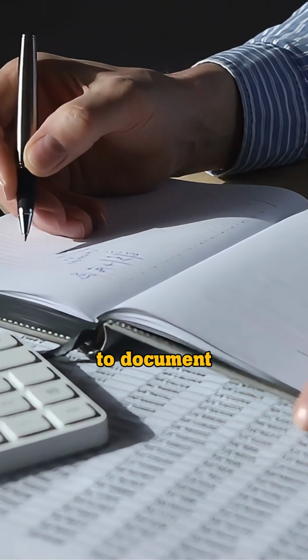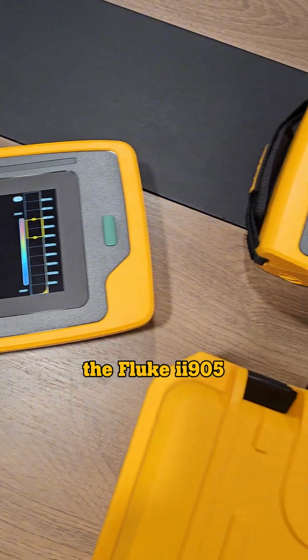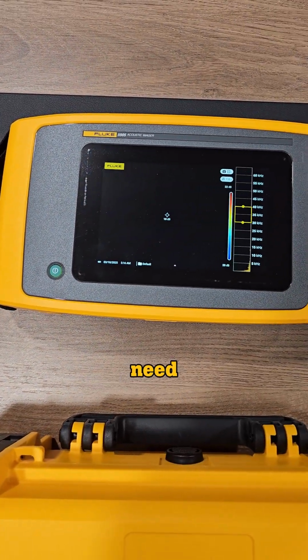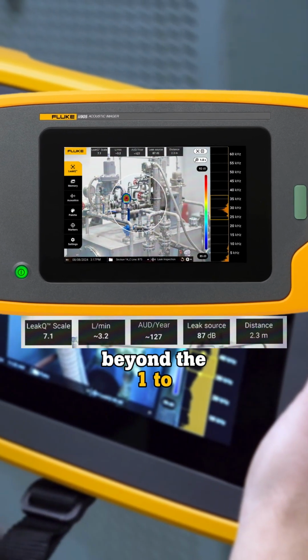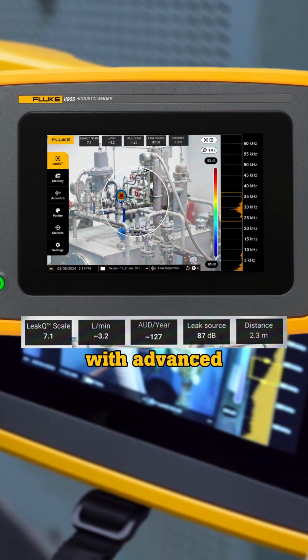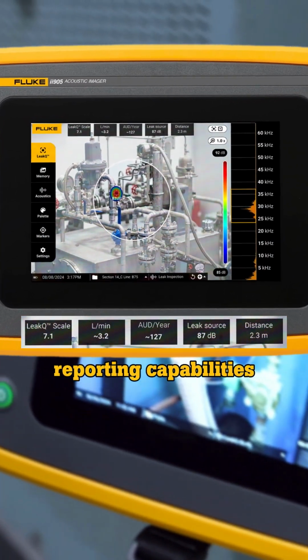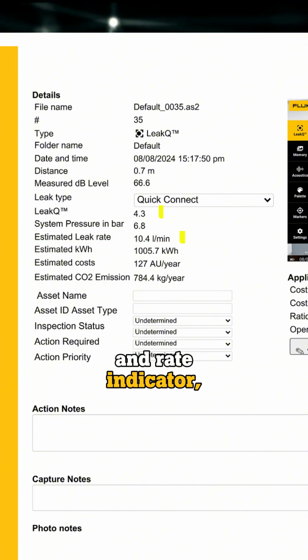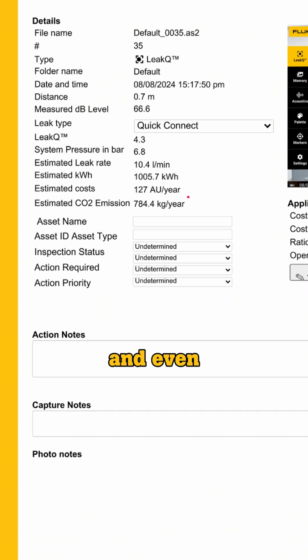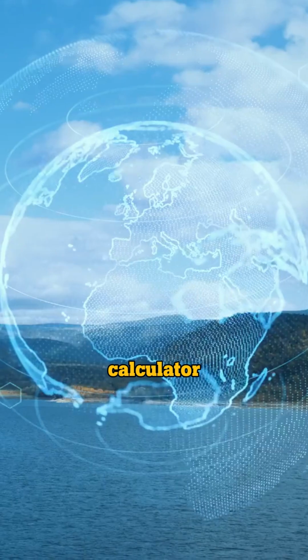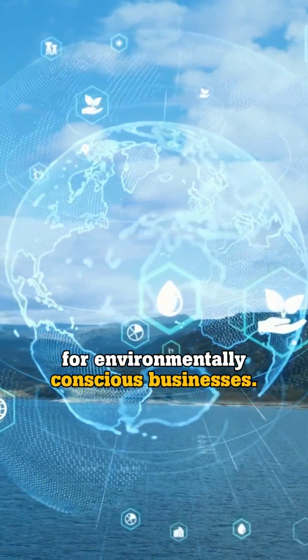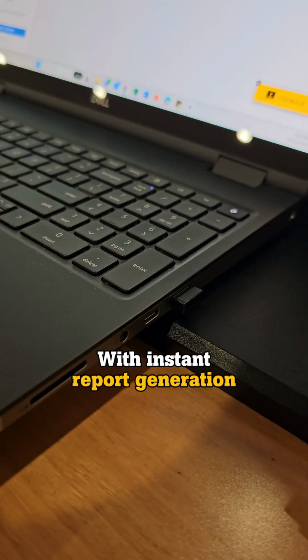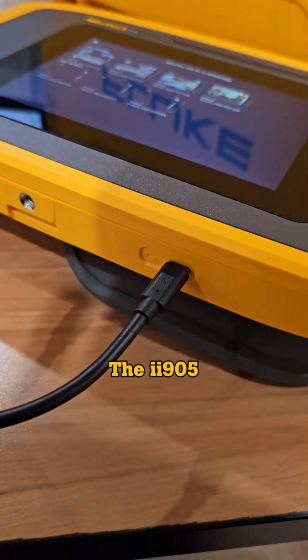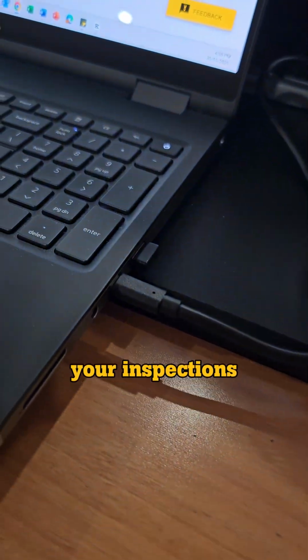If your client or manager needs you to document your leak audit, the Fluke ii905 with LeakQ is the model you need, as it goes way beyond the 1 to 10 leak severity scale with advanced analytical and reporting capabilities, including a leak scale and rate indicator, a leak cost estimator, and even a CO2 emission calculator for environmentally conscious businesses. With instant report generation using pre-built templates, the ii905 doesn't just speed up your inspections, but also your post-audit reporting.